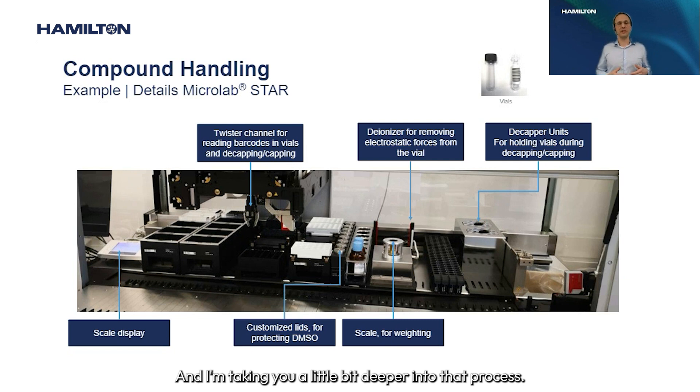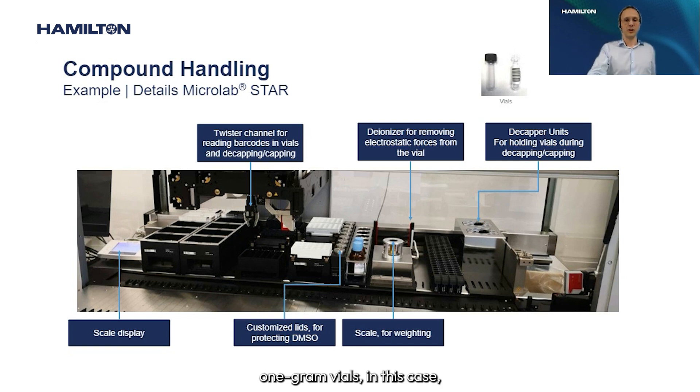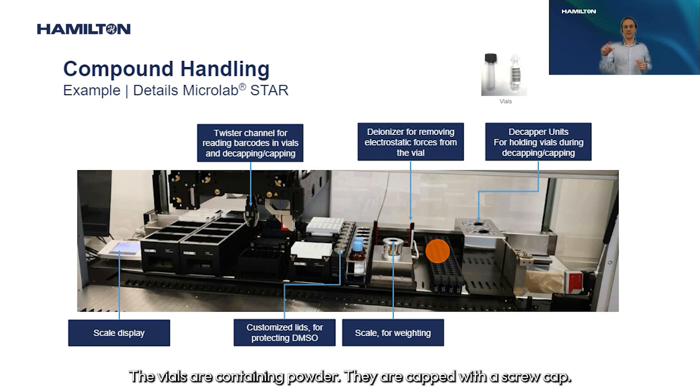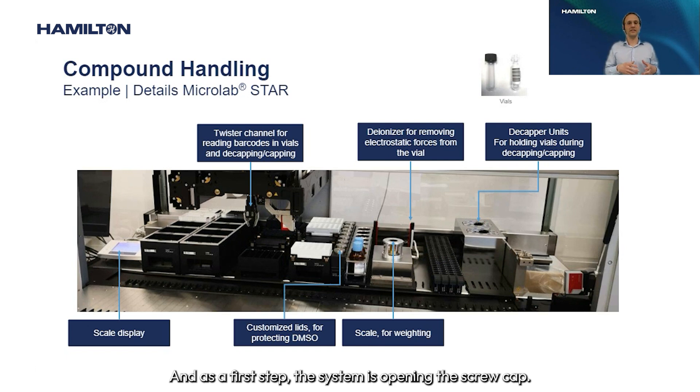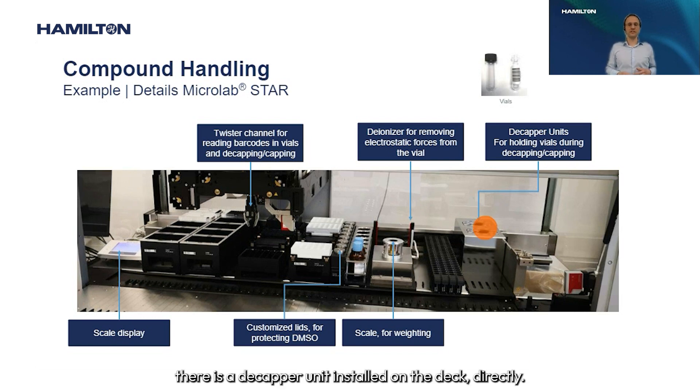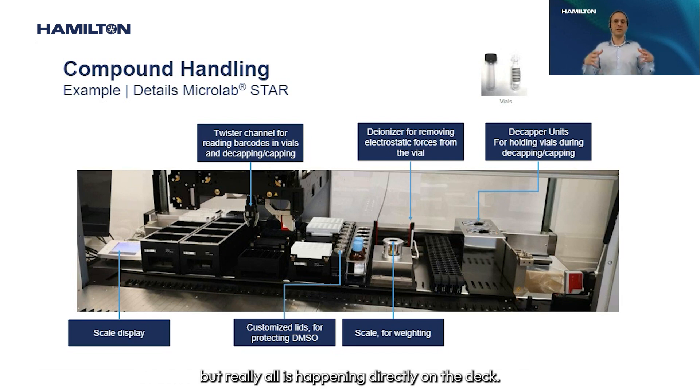At the start of the process, the user loads up to 96 vials — 1-gram vials — onto the liquid handler using 1T carriers. The vials contain powder and are capped with a screw cap. As a first step, the system opens the screw cap using a decapper unit installed directly on the deck, so no additional external device is needed.